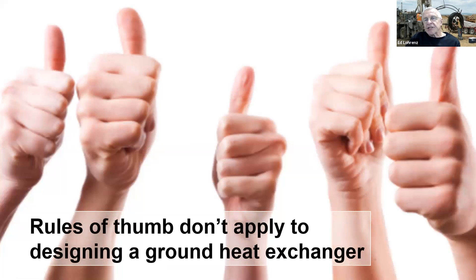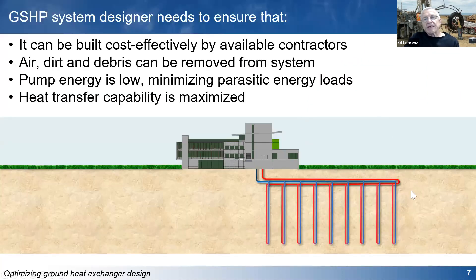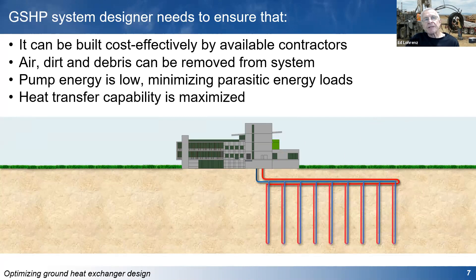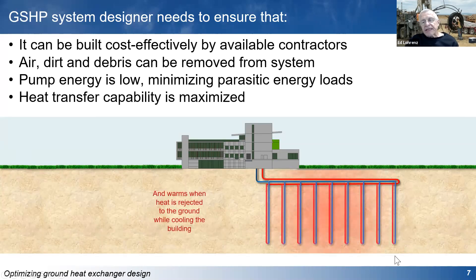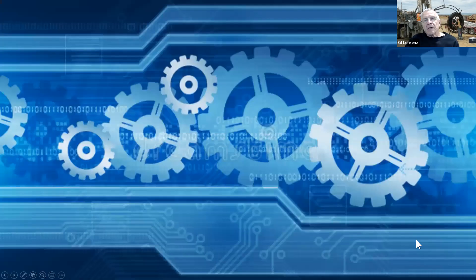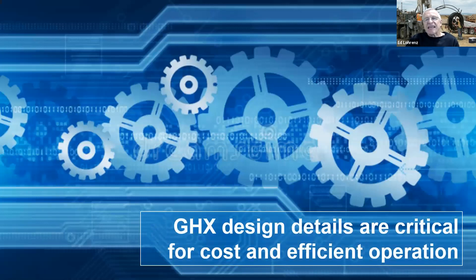Rules of thumb don't apply — same with ground heat exchanger design, same with building mechanical system design. That's simply because you are designing the energy source for the building. You need to design a system that can be built cost effectively by available contractors, that allows you to get the dirt, debris, and air out. You've got to minimize pumping energy and parasitic loads, and you want to maximize heat transfer capability. You're putting a lot of expensive pipe in the ground, and design details are critical for both cost and efficient operation over time.